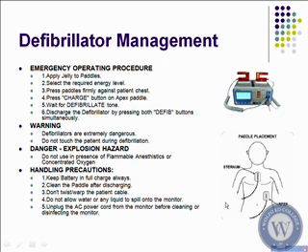It's also explosive danger. There's been several reported cases. I saw this happen as well. Somebody was doused with gasoline from being in a vehicle, and they fibrillated, mostly from the fumes and hypoxia. So en route in the paramedic truck, they fired off one of the paddles, and it ignited the patient, okay, inside the ambulance. The paramedics almost died in the process, so it's something that can be potentially dangerous to you as well in the trauma bay. So just be aware of that.